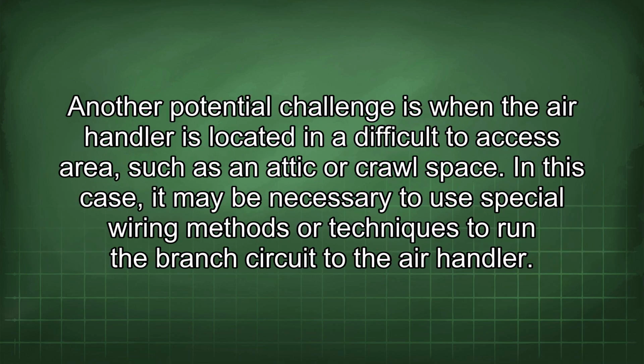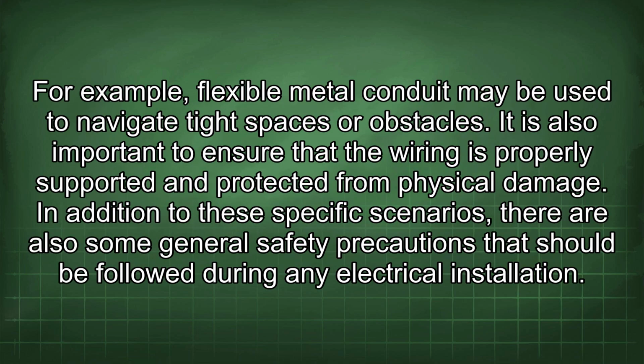Another potential challenge is when the air handler is located in a difficult-to-access area, such as an attic or crawl space. In this case, it may be necessary to use special wiring methods or techniques to run the branch circuit to the air handler. For example, flexible metal conduit may be used to navigate tight spaces or obstacles. It is also important to ensure that the wiring is properly supported and protected from physical damage.